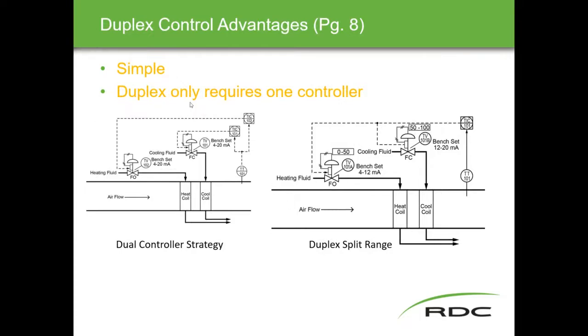What is the advantage of duplex control? Duplex control only requires one controller — one controller signal split to two valves — versus a dual-controller strategy where you need two controllers, one for each valve. The reduction in hardware is a significant benefit, roughly cutting your hardware cost in half.